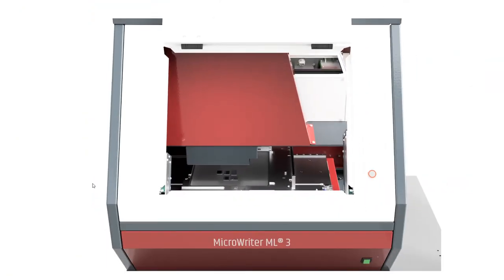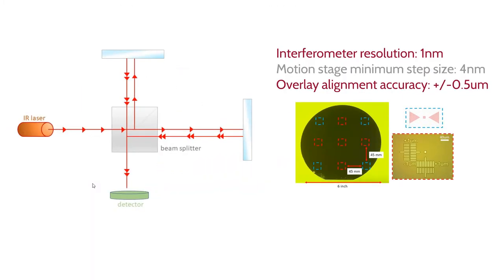Another module I'd like to mention today is the interferometer module. The position of the XY stage is carefully controlled by an interferometer system that we design in-house. It has a maximum resolution of 1 nanometer, and the minimum step size for the XY stage is 4 nanometers. We achieve excellent overlay alignment accuracy of plus or minus 500 nanometers over the entire writing area, even when the machine is used in combination with other lithography tools, such as electron beam or another mask aligner.